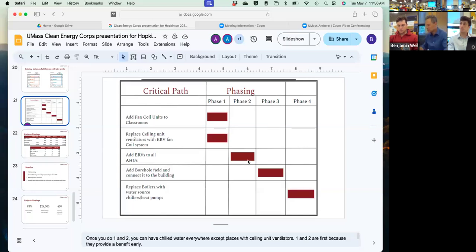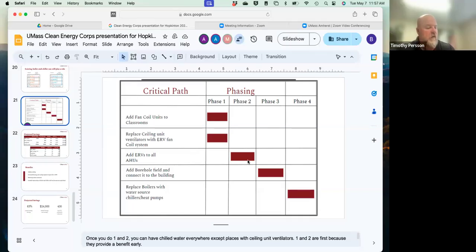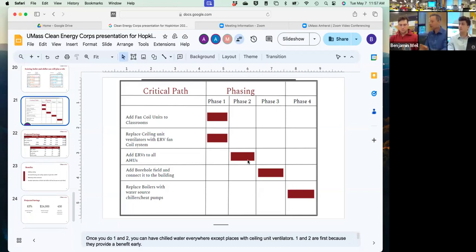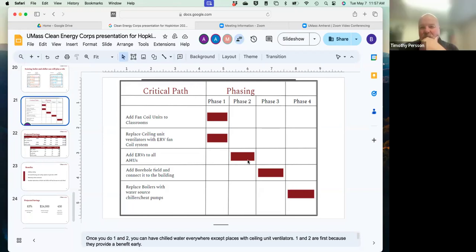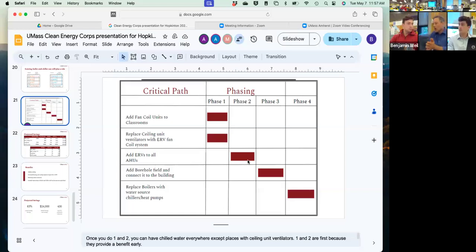Right. But the reason why these ones get a chilled water coil and a hot water coil, even though you've got a bunch of other things with only one coil, at least in theory, is because you can have a separate loop. You've got a simultaneous heating and cooling loop to address days like today, where you don't want to have to change over the whole temperature of that whole loop. But once you move into all cooling, you can then send chilled water through what is now your hot water loop.